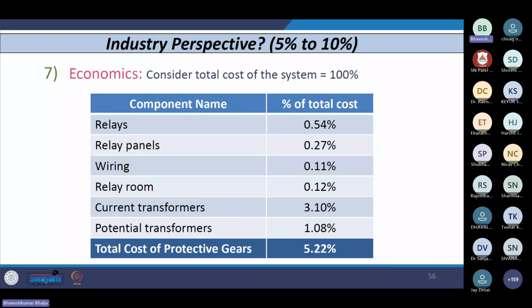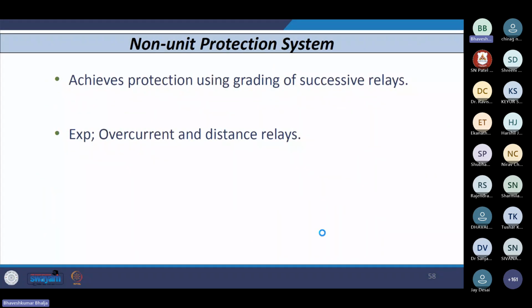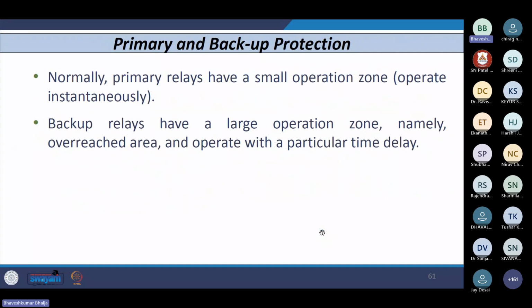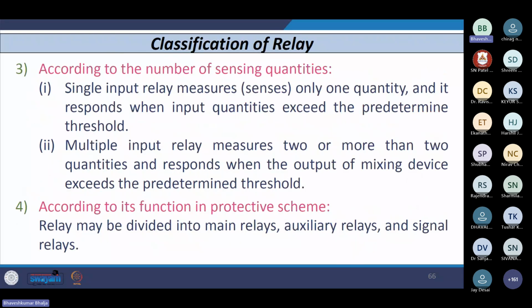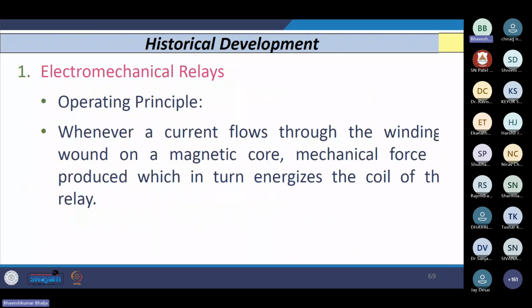So you need to understand that whenever you consider the cost of the system to be 100%, the cost of the protective gear, which includes your relay, CT, PT, wiring, everything, should not be more than 5 to 10% of the total cost. Breaker cost is separate, right? That is not included here because it comes under the switchgear part. So this needs to be followed. Okay, now just a minute. Let me check.